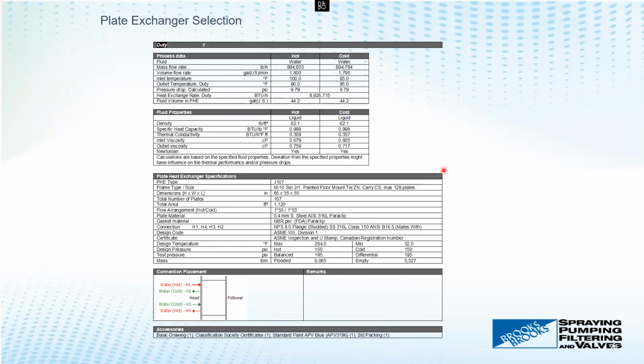But here's your machine down here, this is everything that it solved for us. We've got a frame, this particular frame was an M10, which was able to handle 129 plates. The plates are down here, 0.4 millimeters thick, made out of 316 stainless steel. Paraclip is those clip-in gaskets we talked about a few minutes back. We have the dimensions, 85 inches tall, 35 wide, 55 deep. So 107 plates are going to make 55 inches with their gaskets.